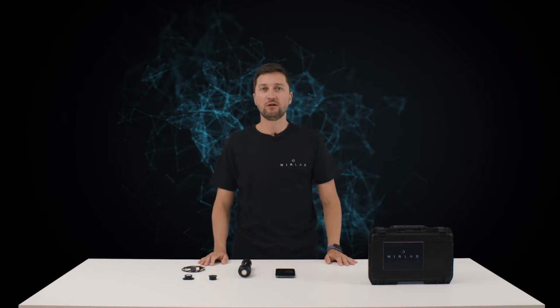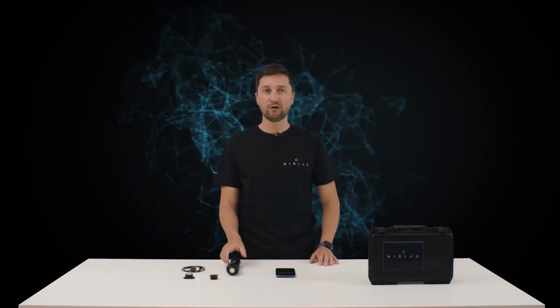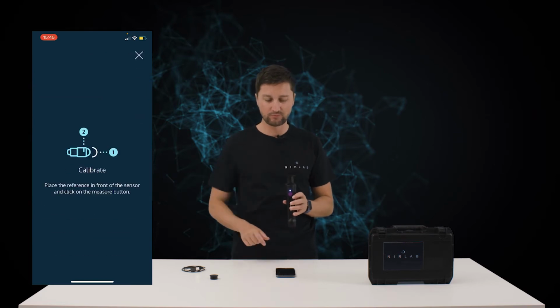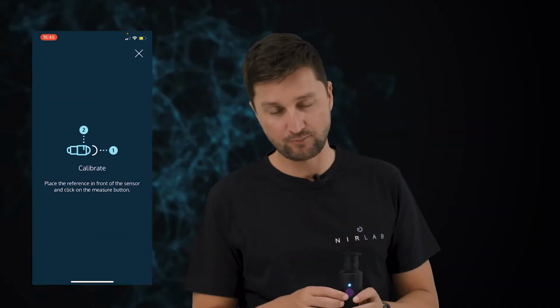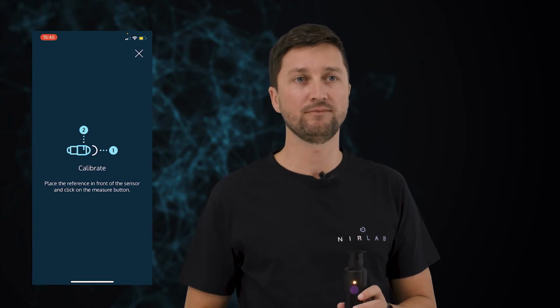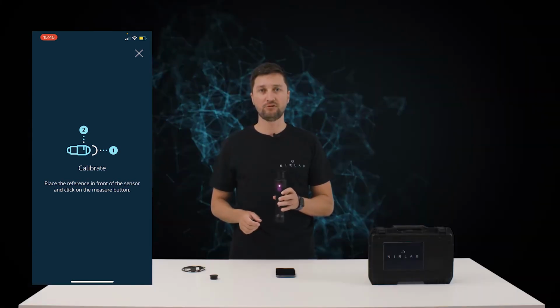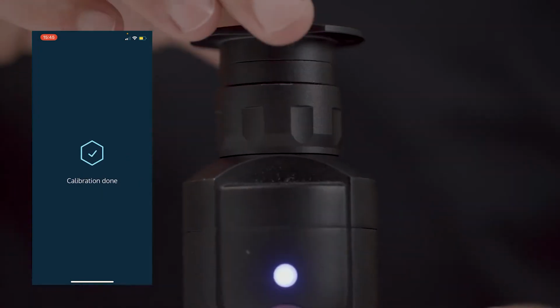At every start of the app, you are requested to calibrate the device. This is a very simple step that is done in a few seconds. To perform calibration, I simply need to apply the white reference mirror on the NIRLAB device, then click on the Calibrate button on the mobile app, and then push the NIRLAB device button. After a few seconds, the calibration is done and we are ready for our analysis. It is recommended to calibrate regularly. The mobile app will inform you when it is necessary.